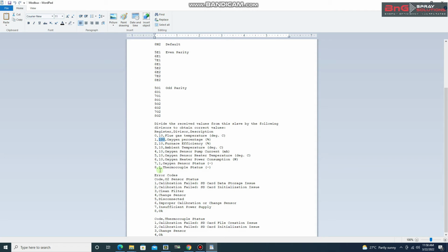And if the oxygen analyzer has any issues, these issues will show up on the LCD, and these issues will also reflect in this entry and this entry. So number 8 is for the thermocouple status, and number 7 is for the oxygen sensor status. So for example, if it is okay, then this oxygen sensor status will show up as 8. If thermocouple is okay, it will show up as 4. If there is any other error, this error code that is given here will be reflected in whatever data is received in number 7 and number 8.